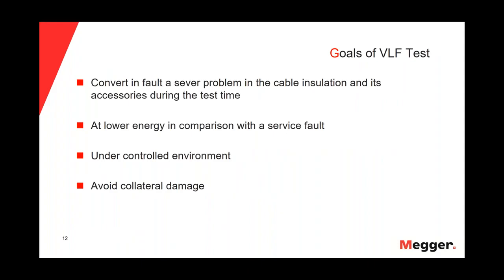The goal of the VLF test is to convert into a fault a severe problem in the cable insulation and its accessories during the test time, and at lower energy in comparison with a service fault. So this is very important. And we will do this under a controlled environment, and we will avoid, of course, collateral damage.